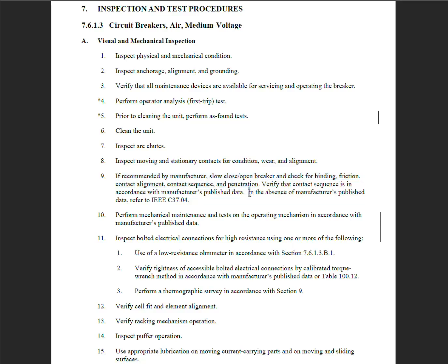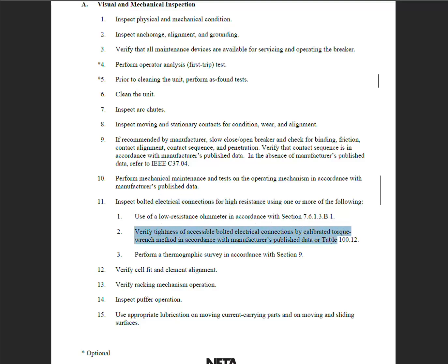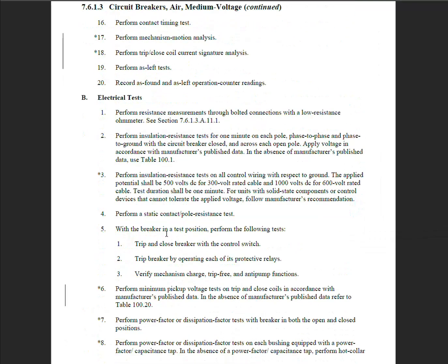In the absence of published literature, follow an IEEE doc. It doesn't even give you a NETA specification. It tells you go to IEEE if the manufacturer ain't got something. Okay. And then perform mechanical maintenance in accordance with manufacturer's data. All right. Perform electrical connection high resistance testing. This right here, all your torque checks in accordance with manufacturer's data. Okay, lots of stuff. It tells you that's all mechanical, right?